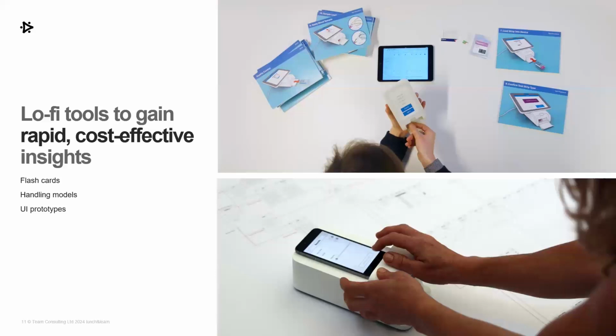Basically, we were able to produce a super low fidelity simulation of the final product experience to understand stakeholders' expectations and comprehension of the system. And this was really very, very early stage in the development. We conducted smaller scale studies internally to answer very specific questions, i.e. what size and position of sample port is most likely to encourage the user to apply the correct amount of blood.